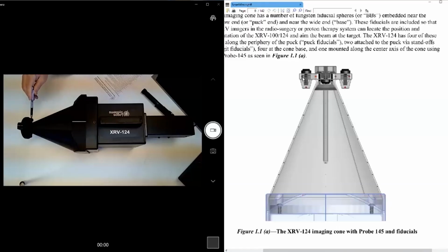In order to maximize the flexibility of the XRV-124 with various styles of image guidance, 11 fiducials are available on the image cone. All BBs are 2.5 mm in diameter and are made of tungsten steel alloy. To begin with, the puck has 4 embedded fiducials that form a plane through its center. This plane is the origin of the z-axis of the XRV-124 measurement coordinate system. It's the place where z equals 0 within the BeamWorks software.